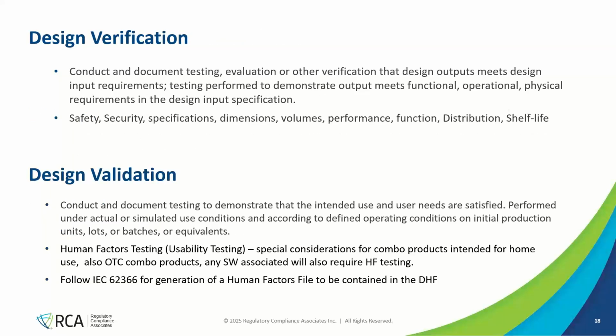And then design verification is the testing or other assessment, documentation, evaluation, that the outputs that we have now documented meet the requirements. So every requirement should have some sort of verification evidence. These are functional, operational, physical, things as simple as dimensions. You verify them, and that is design verification. I do say here, consider safety, security, specification, dimensions, volumes, but then you have things like performance, which is delivery plus or minus this many milliliters, or delivery within a certain amount of time. Those are performance. Function is the ability for it to do those things, not necessarily within a time frame, but just that it does it. But you also need to consider distribution, shipping studies, packaging design, and shelf life.